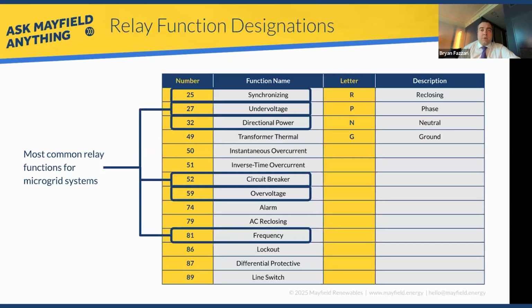We tend to name our products after the primary element that relay is built around. In this case, the 751 would be the 51 element. However, unlike electromechanical relays that a digital relay would replace, these products are capable of doing many of these elements.